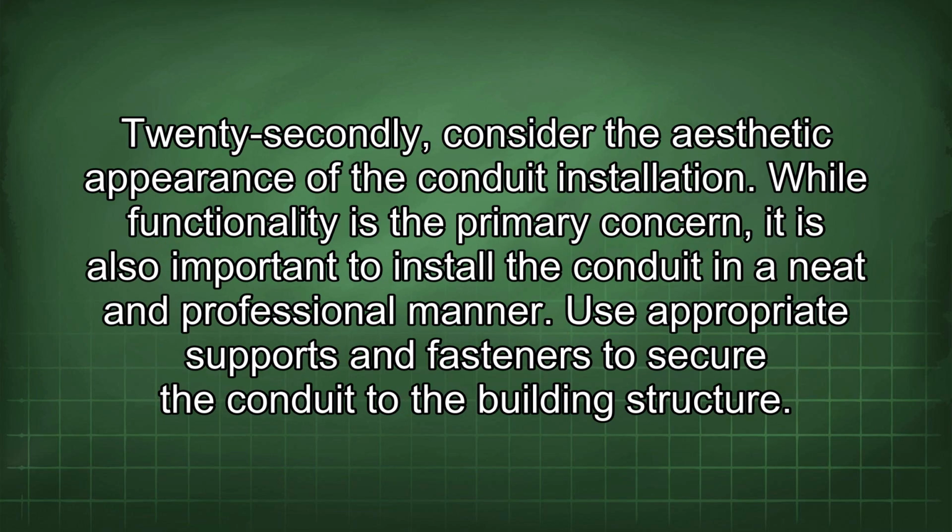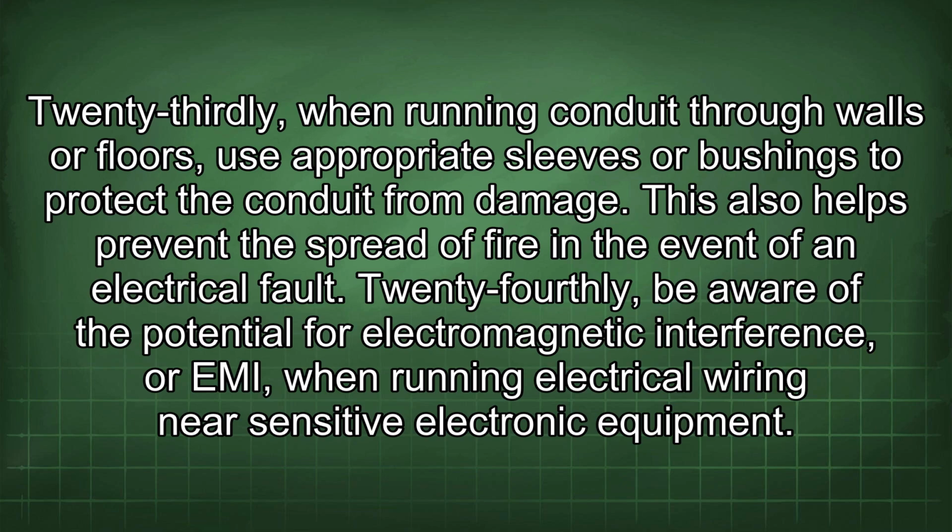22ndly, consider the aesthetic appearance of the conduit installation. While functionality is the primary concern, it is also important to install the conduit in a neat and professional manner. Use appropriate supports and fasteners to secure the conduit to the building structure. 23rdly, when running conduit through walls or floors, use appropriate sleeves or bushings to protect the conduit from damage. This also helps prevent the spread of fire in the event of an electrical fault.